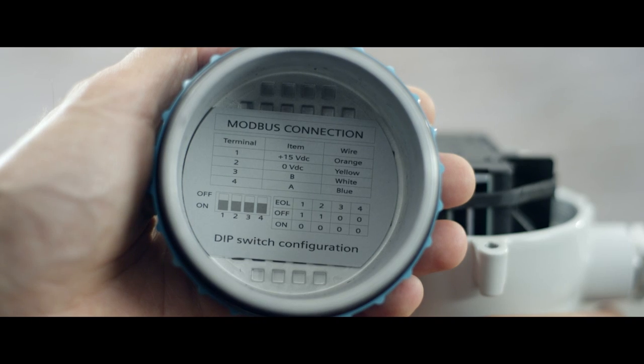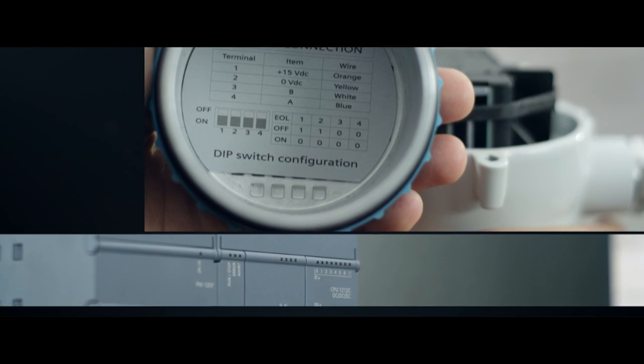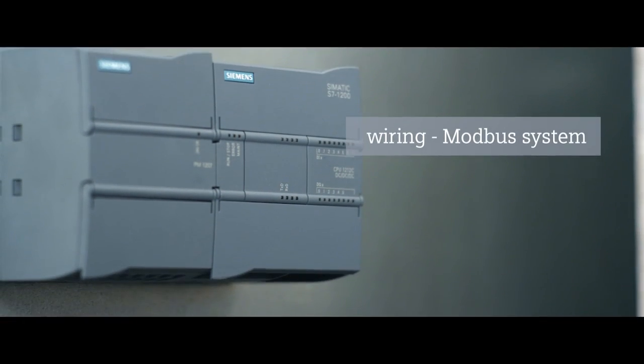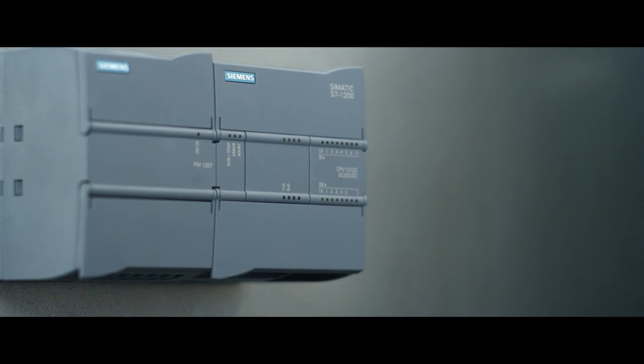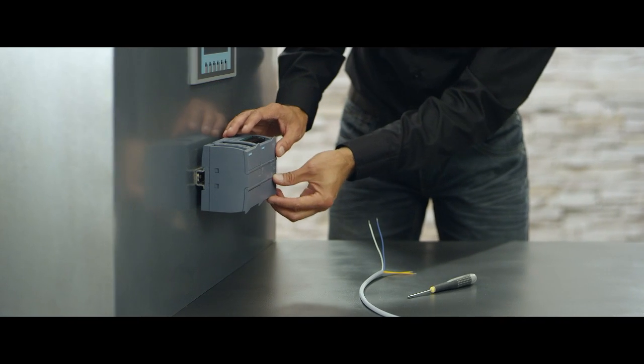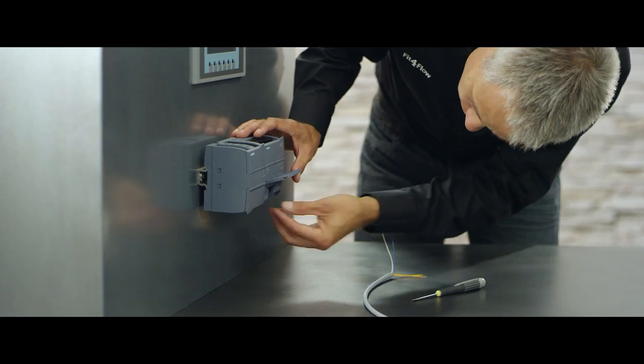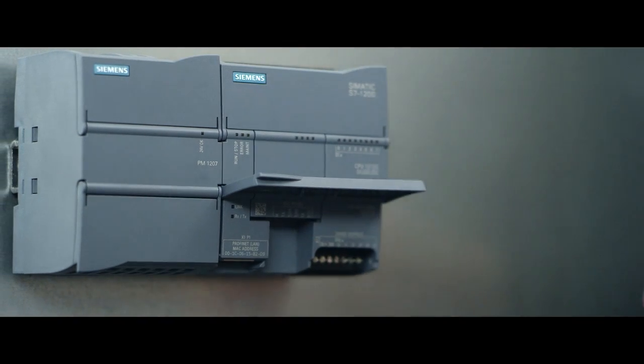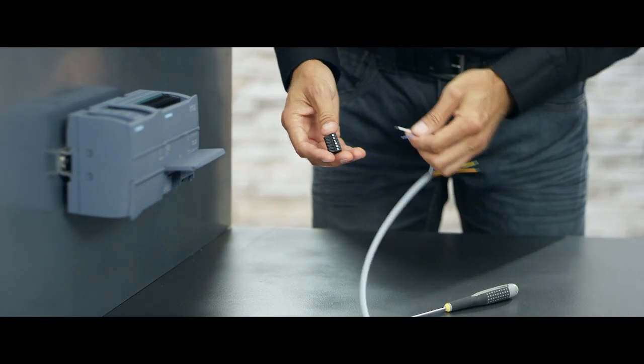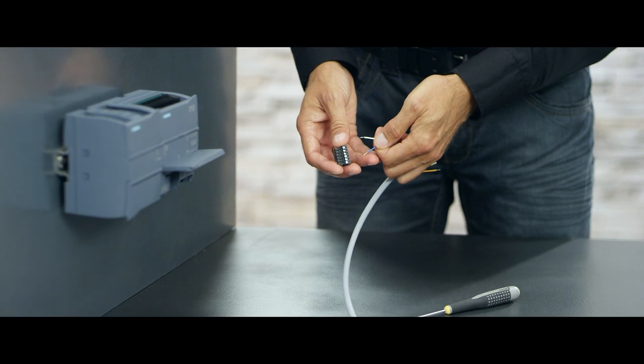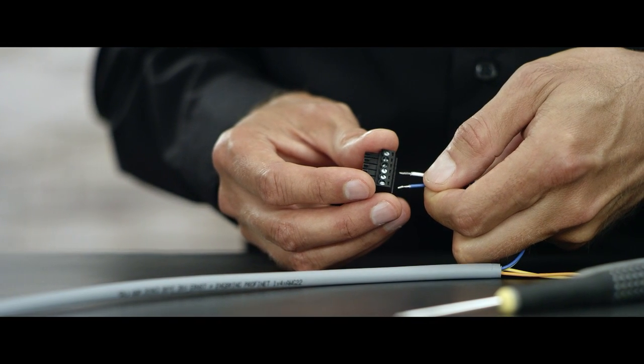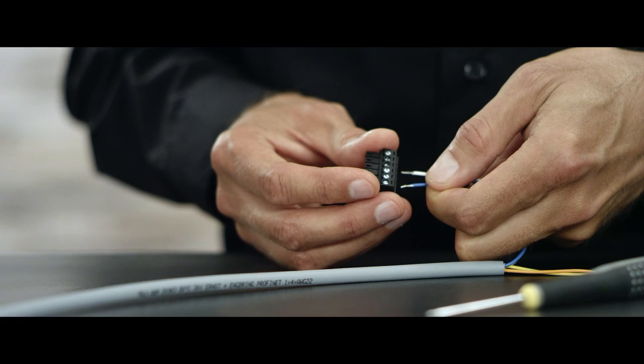You can find a respective plan on the back of the cover and in the operating manual. In order to establish the wiring between the SITRANS FC410 and the automation system in our example, the 4-wire cable is connected directly to the integrated communication module and the 24V connection of the PLC. Please refer to the operating manual for the correct wiring.